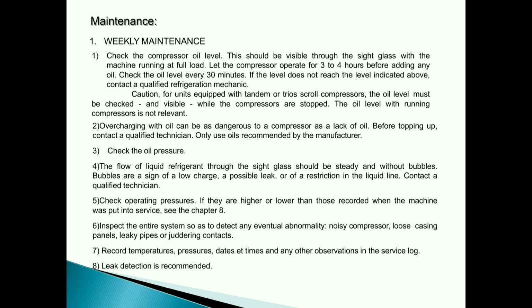5. Check operating pressures. If they are higher or lower than those recorded when the machine was put into service, see Chapter 8. 6. Inspect the entire system so as to detect any eventual abnormality, noisy compressor, loose casing panels, leaky pipes or juddering contacts. 7. Record temperatures, pressures, dates and times and any other observations in the service log. 8. Leak detection is recommended.